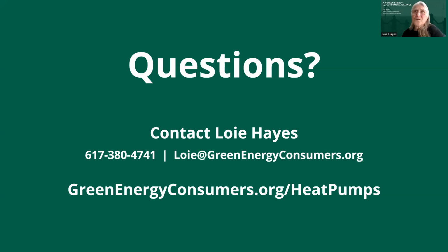With older boilers and furnaces, we knew 68, 69, or 70 degrees would keep us comfortable. But with a heat pump, since it's a different technology for distributing heat, you may need it at 71 or 73 to adequately move the air around. You can also control the speed of the fan.